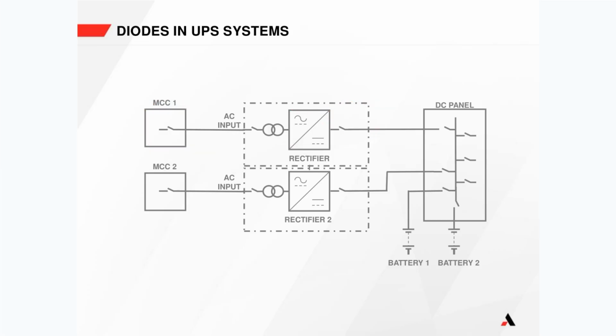But when you have two chargers in parallel that are connected without any way of separating the two feedback circuits, this charger here could be sitting at 130 volts, and this charger here could be sitting at 135 volts. The feedback for this system will say, wait a minute, through this DC bus I am seeing 135 volts, but somebody set me at 130 volts. I'm going to phase off a little bit until I get down to 130 volts.